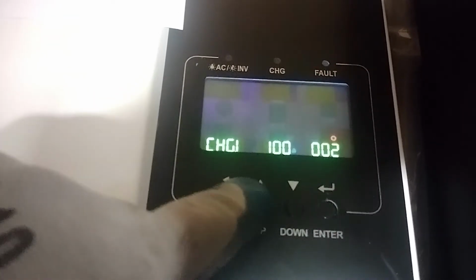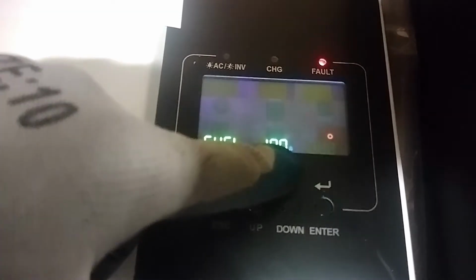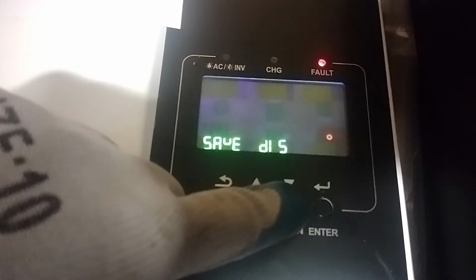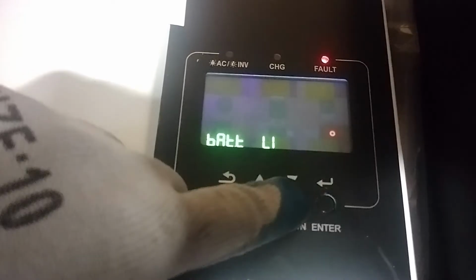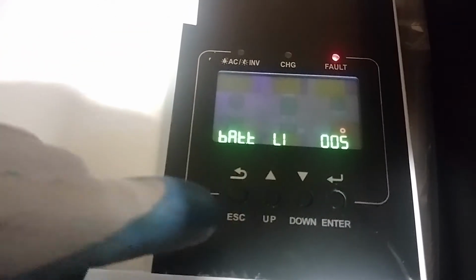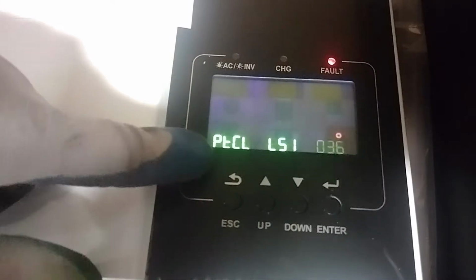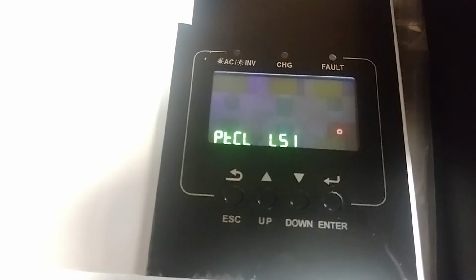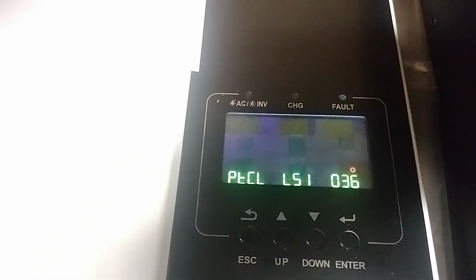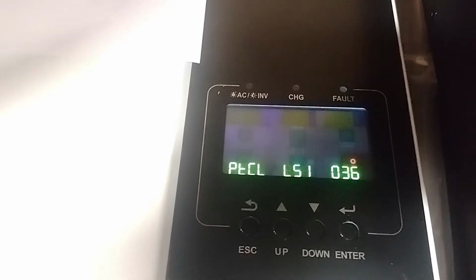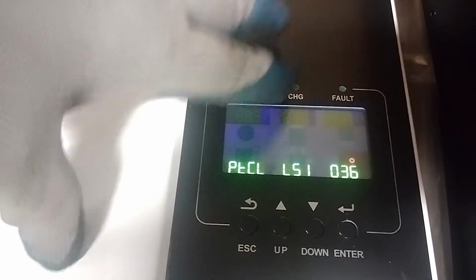So number one thing to note is this is the charging current, which is 100 amps, but that isn't what it is at the moment. So this is the lithium setting, so we're going to change it, note this: this is the right setup, protocol 51, which is what the Growatt Inverter ES series uses with the Hope Growatt battery. But then on startup, this gives you an error.